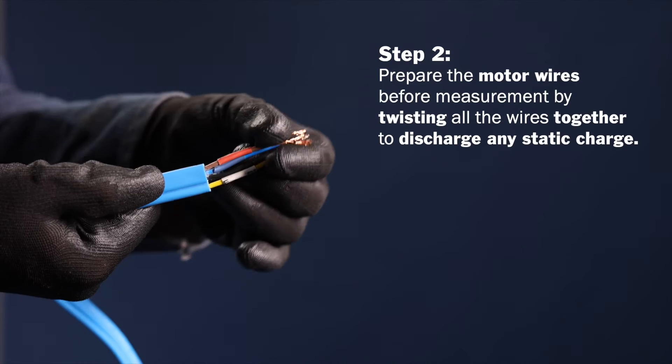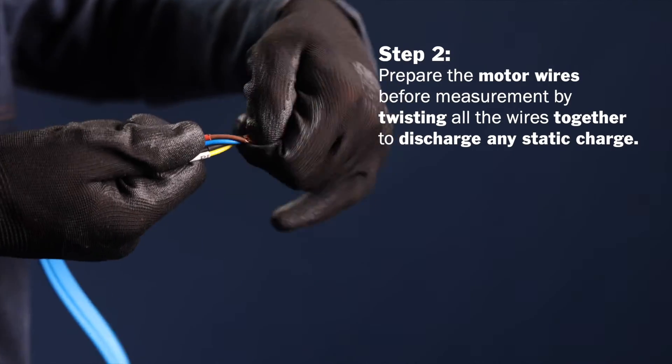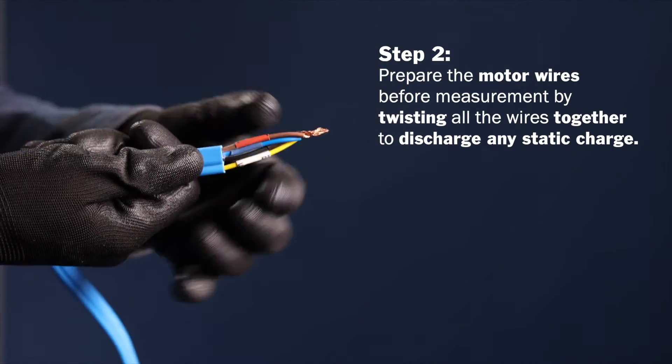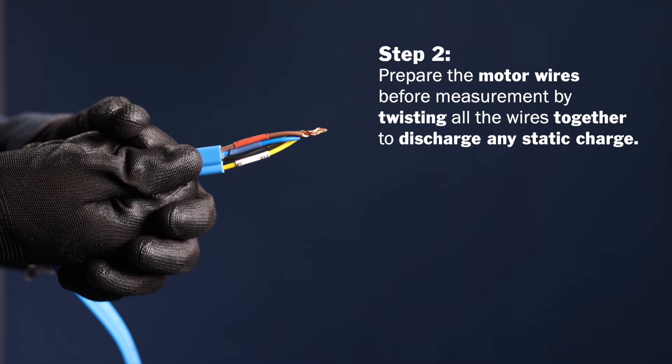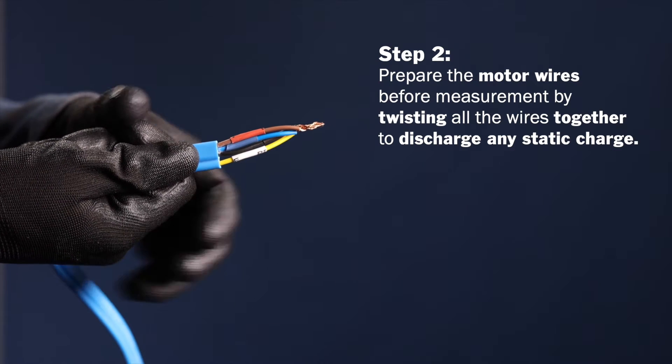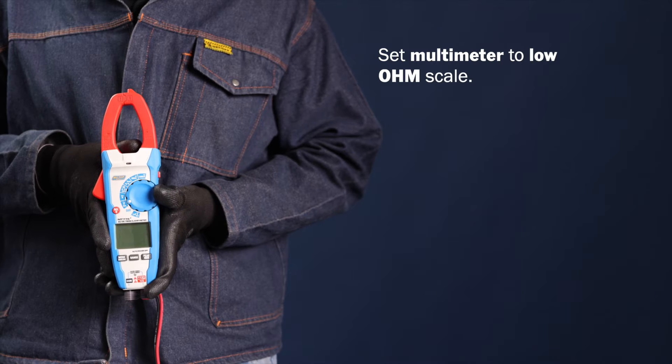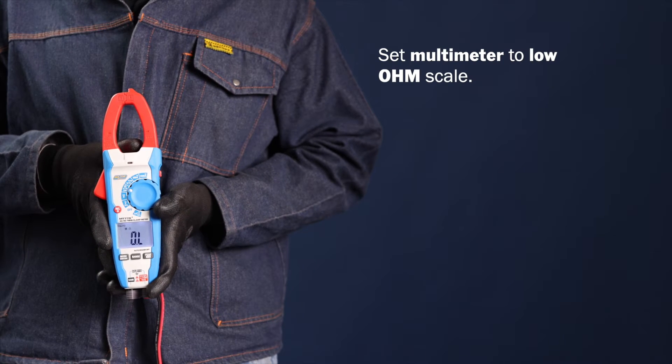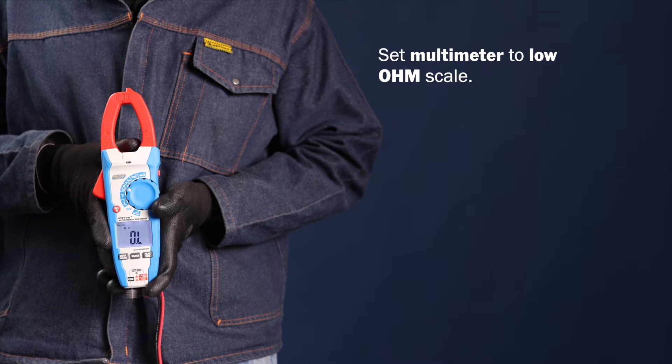Step 2. Prepare the motor wires before measurement. Start by twisting all the motor wires together for a few seconds to discharge any possible static charge in the motor. Next, set your multimeter on a low ohm scale capable of measuring up to 100 ohm resistances.